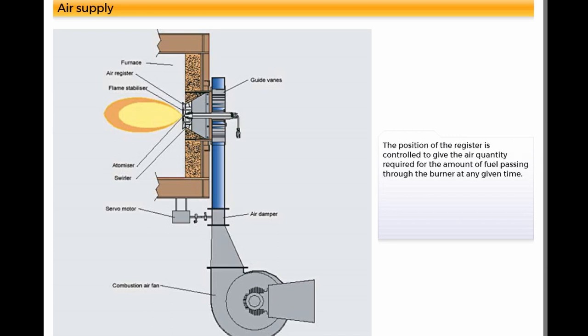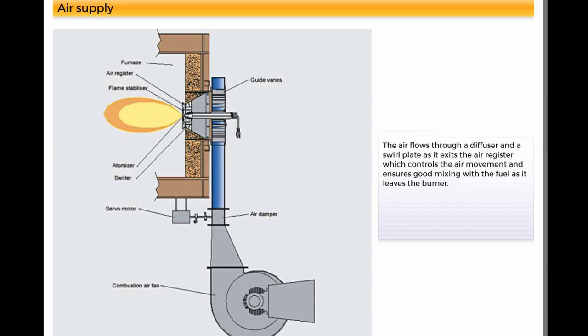The position of the register is controlled to give the air quantity required for the amount of fuel passing through the burner at any given time. The air flows through a diffuser and a swirl plate as it exits the air register which controls the air movement and ensures good mixing with the fuel as it leaves the burner.